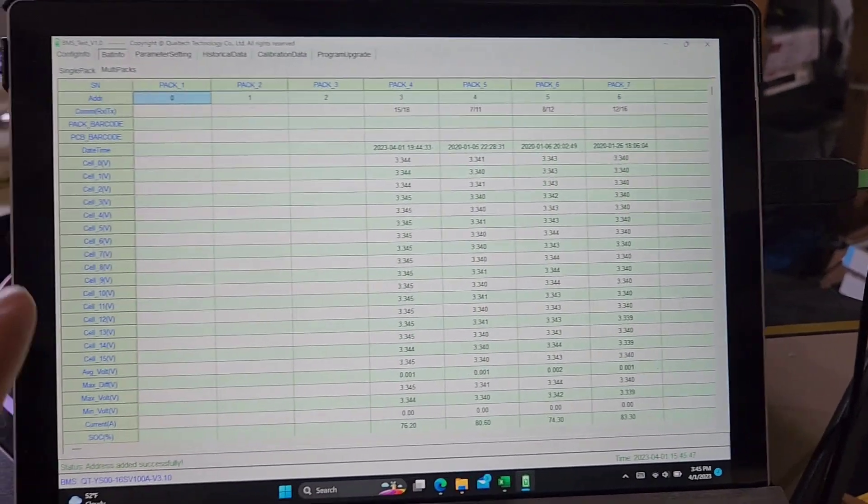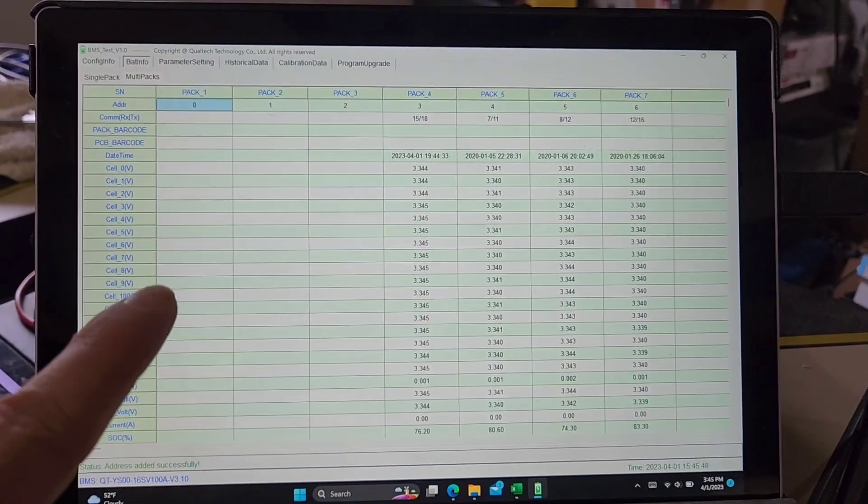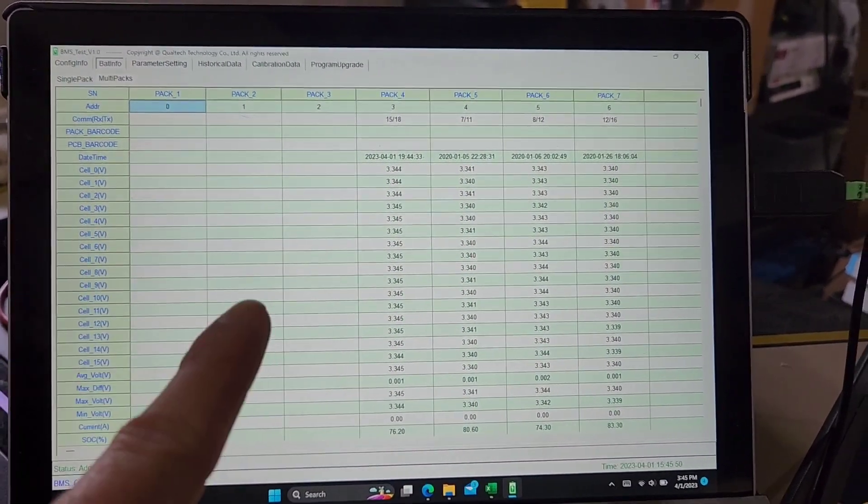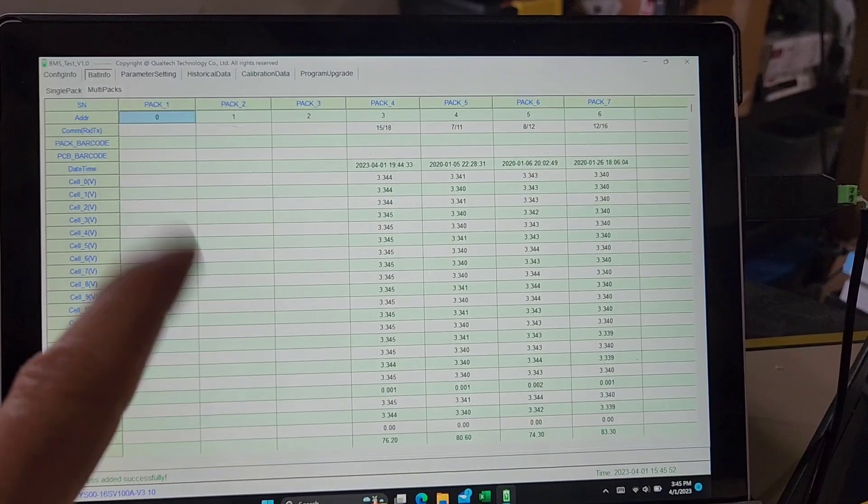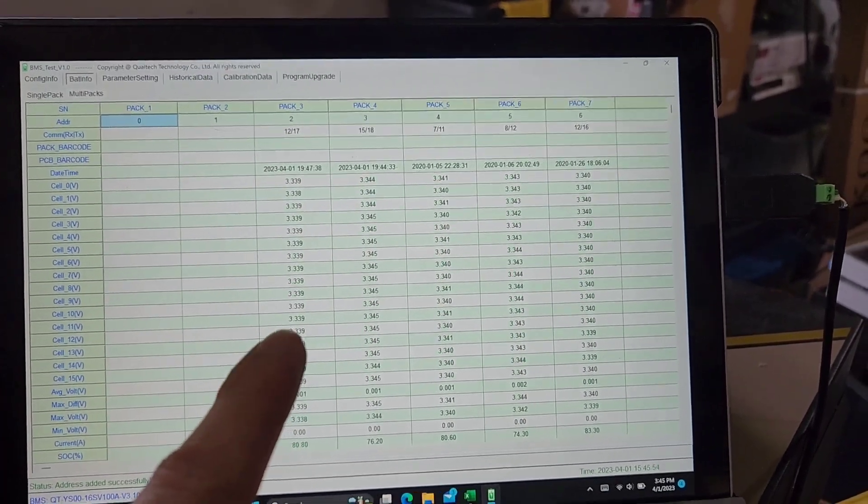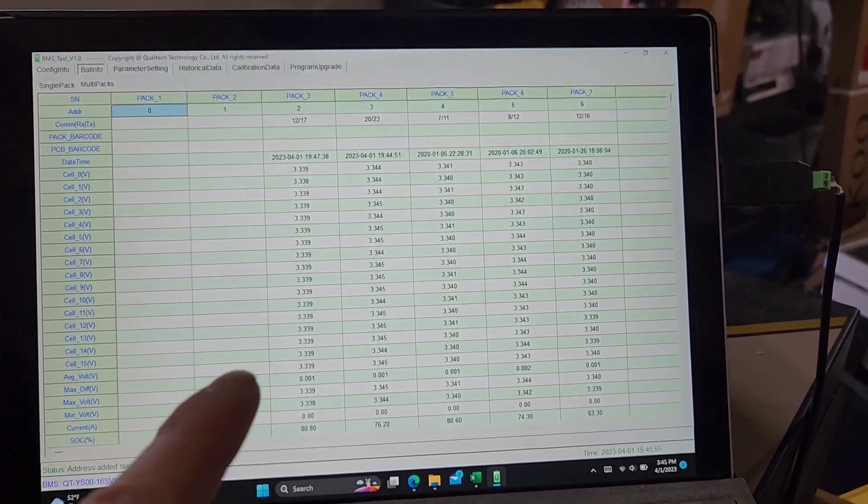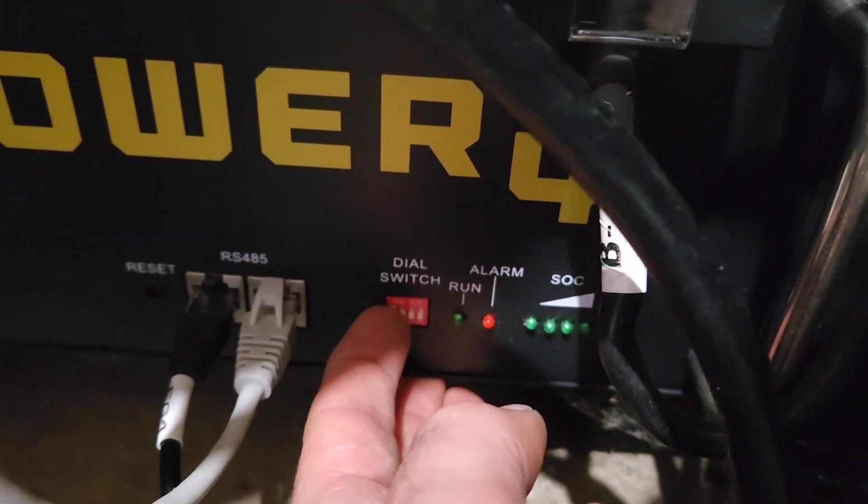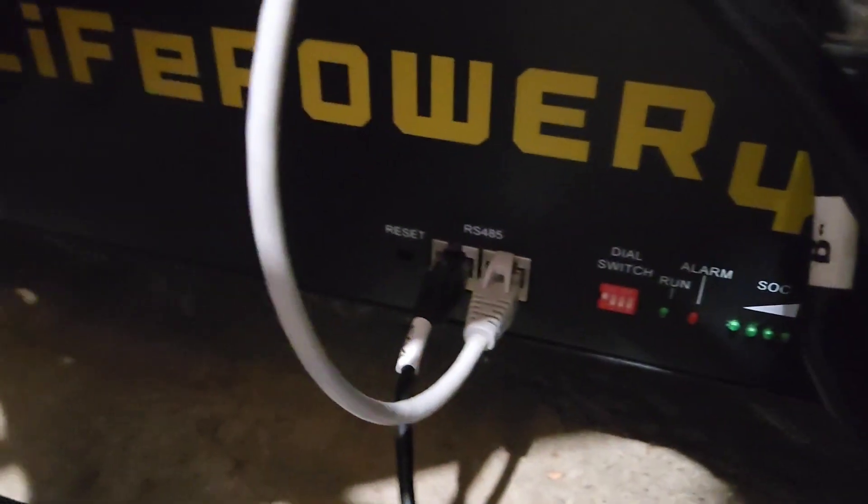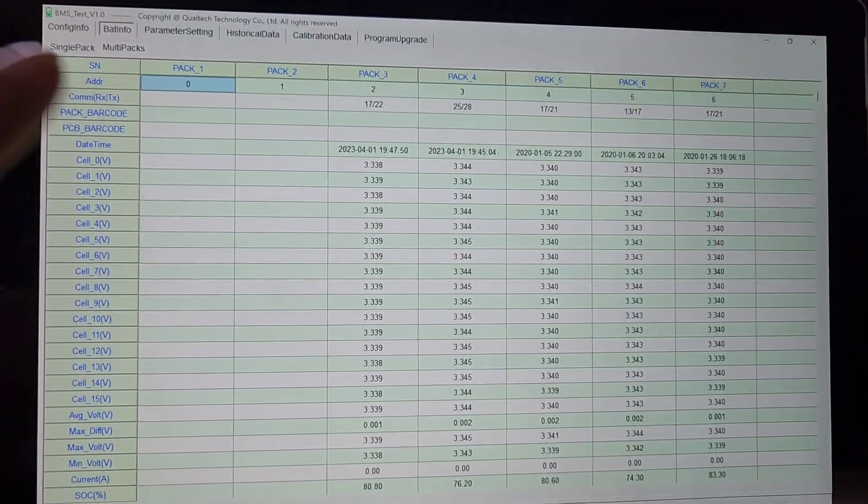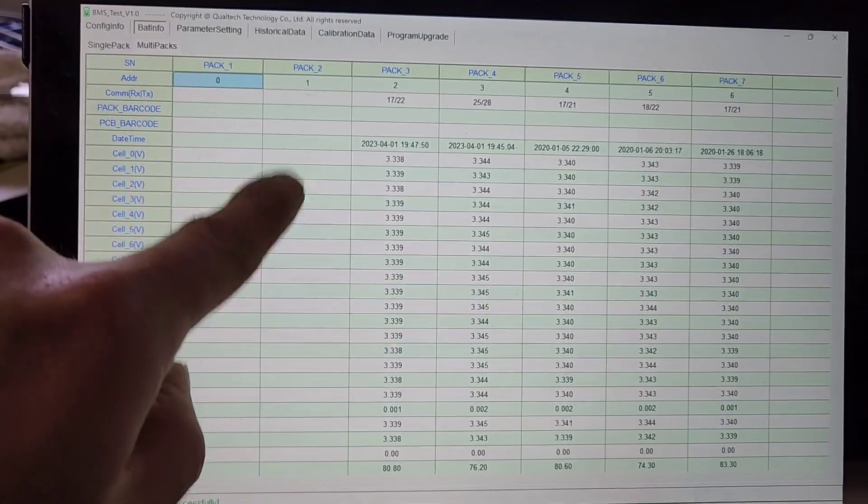Now remember, zero is the main battery that talks to the inverters. One is the backup address that I use to switch it to, then two. So now if I come down here and I hit this dip switch from all down to one, one up, flip the breaker, and then it should appear on one.